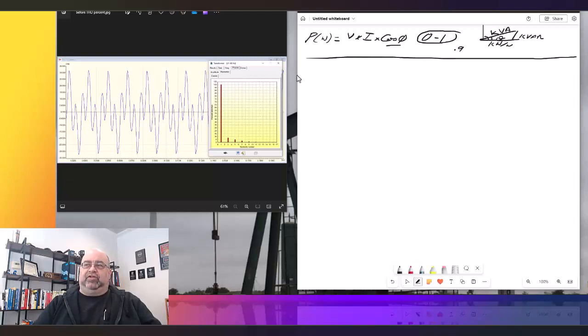The voltage present, since we need to know voltage, when we did the test, was 62 volts between the primary 60 hertz, but it also showed up as tripling. Then out here, when I hit the ninth harmonic — which is the third harmonic of the third, so fundamental times three times three — that turned out to be 12 volts.